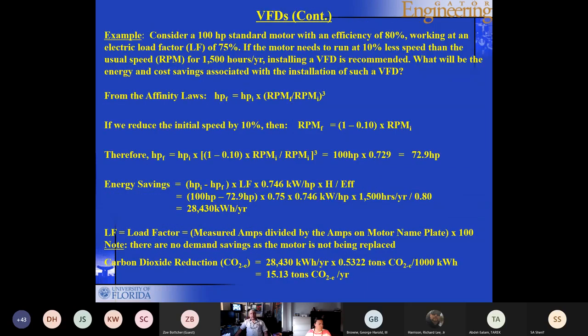Now, if you look at the way we're going to calculate the savings, again, we're going to use a 100 horsepower standard motor with an efficiency of 80%. It's working at an electric load factor of 75%. Again, the load factor is the ratio between the amperage you measure across the motor windings divided by the nameplate amperage. If the motor needs to run at 10% less speed than usual, let us say that it wants to run 10% less speed for about 1,500 hours of the year. So if you install a variable frequency drive, that would probably help you. The question is, what will be the energy and cost savings associated with installing such a variable frequency drive?